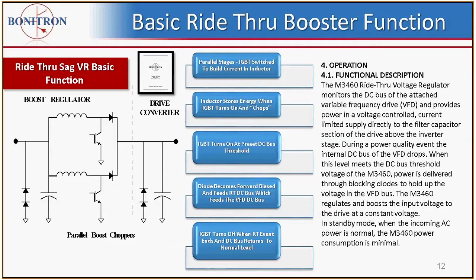There's parallel stages in the ride-throughs when you get over 50 kilowatts, so even if you do lose one stage, there is still some ride-through capability. It's degraded, but as long as you have one stage left, it will boost with that stage. So there is redundancy even within the greater than 50 kilowatt 3460 units.